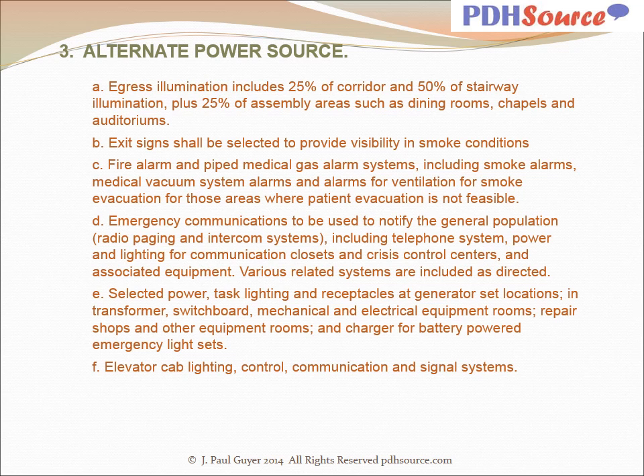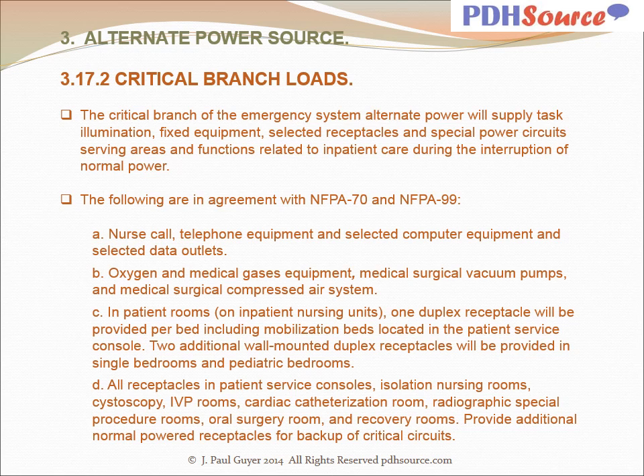Selected power, task lighting, and receptacles at generator set locations, in transformer, switchboard, mechanical and electrical equipment rooms, repair shops and other equipment rooms, and chargers for battery-powered emergency light sets, elevator cab lighting, control, communication, and signal systems. The critical branch of the emergency system alternate power will supply task illumination, fixed equipment, selected receptacles, and special power circuits serving areas and functions related to inpatient care during the interruption of normal power. The following are in agreement with NFPA 70 and NFPA 99. Nurse call, telephone equipment, and selected computer equipment and selected data outlets. Oxygen and medical gases equipment, medical surgical vacuum pumps, and medical surgical compressed air system.